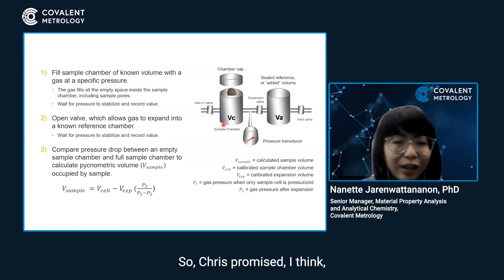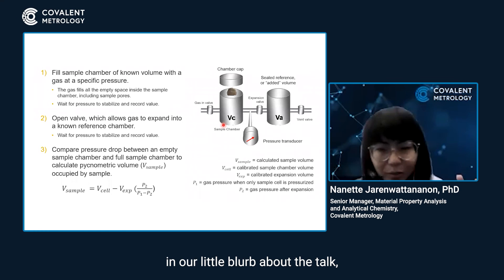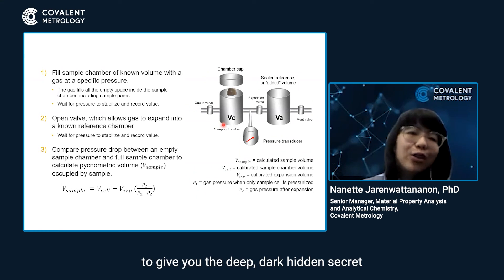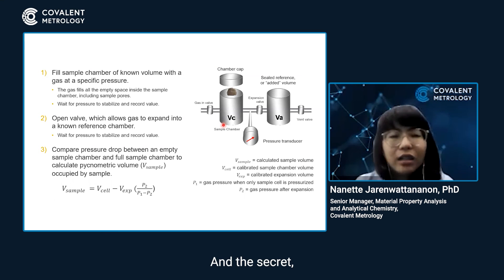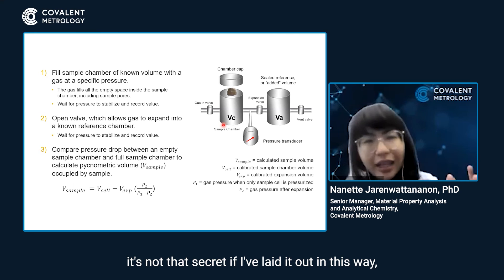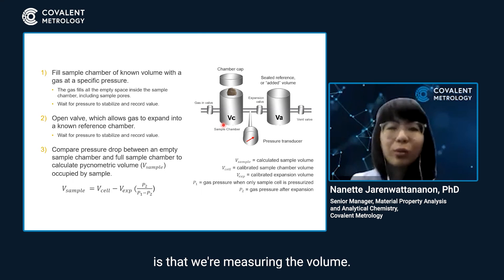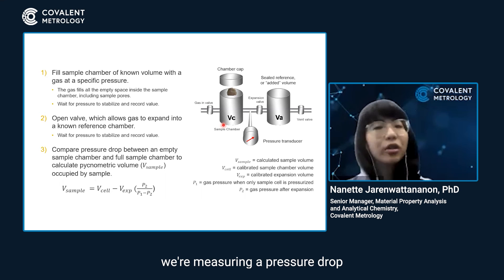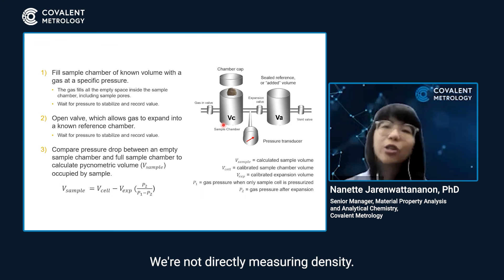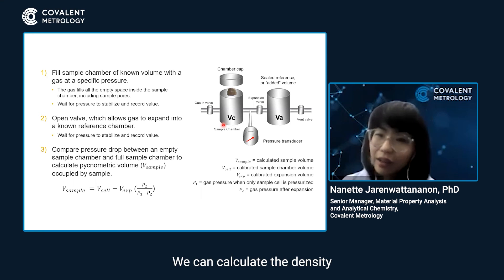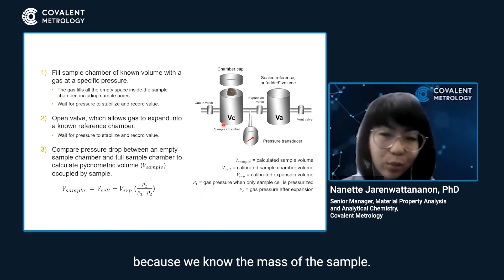Chris promised to give you the deep, dark, hidden secret of pycnometry. The secret — and it's not that secret if I've laid it out this way — is that we're measuring a pressure drop and a volume of the sample. We're not directly measuring density. We can calculate the density because we know the mass of the sample.